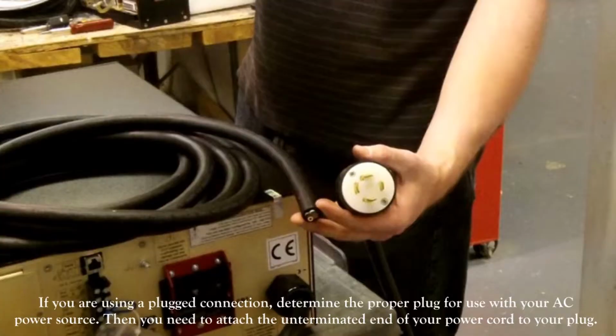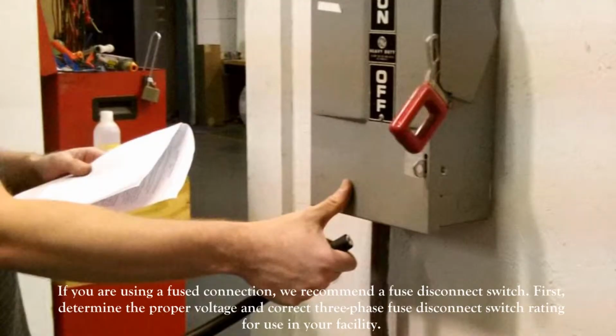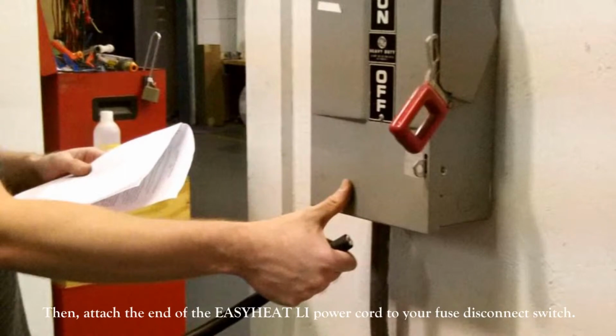If you're using a plug connection, determine the proper plug for use with your AC power source. Then you need to attach the unterminated end of the EASYHEAT LI power cord to your plug. If you are using a fuse connection, we recommend a fuse disconnect switch. Now first, determine the proper voltage and three-phase fuse disconnect switch rating for use in your facility. Then, attach the end of the EASYHEAT LI power cord to your fuse disconnect switch.